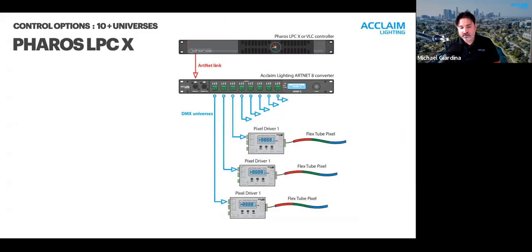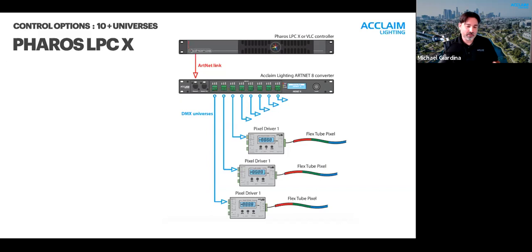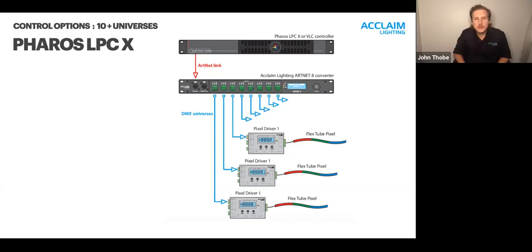Looking at how LPC X can break out into standard hardware DMX: the Acclaim Artnet 8 device takes eDMX from the Pharos device and converts it to eight standard DMX outputs. From there you can run DMX directly to your fixtures or to DMX splitters. Since there are eight ports on the Artnet 8, you divide your total DMX universes by eight to determine how many Artnet 8 units you'll need — for a 20-universe system, you'd need three.